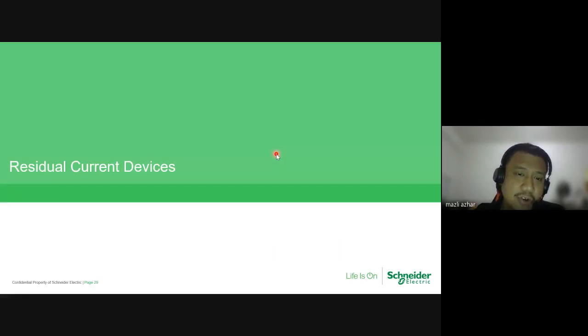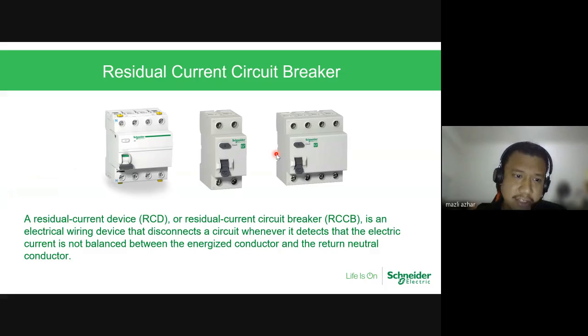All right, so we go to the residual current device. Okay, done with the MCB. So what is the residual current device or residual current circuit breaker? It is an electrical wiring device that disconnects a circuit whenever it detects that the electric current is not balanced between the conductor and return neutral. So my simple layman term is, what goes into the load must come back at the same value. So if, let's say, 13 amps goes to the load, what comes back to the MCB must be 13, not more, not less. So this is how the principle of RCD comes into play.